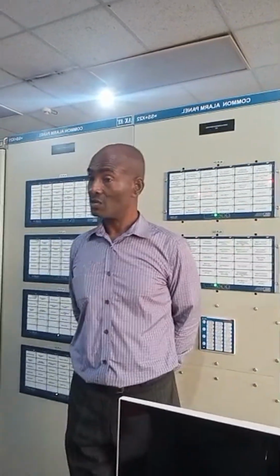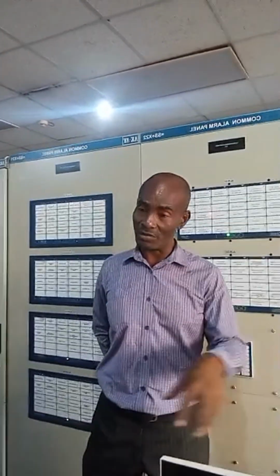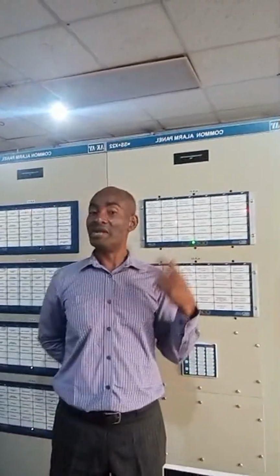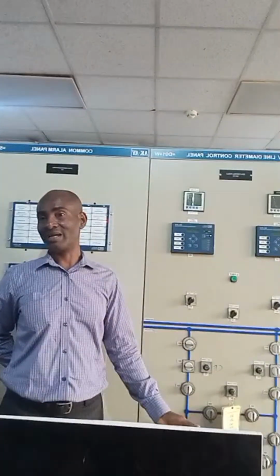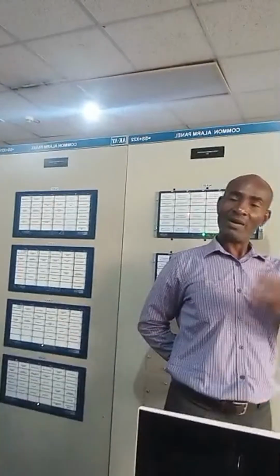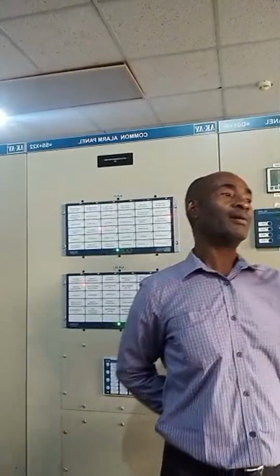Is that okay? You get the gist? If there is no quenching medium, for those highly rated breakers, that's why we have oil circuit breakers, OCB. Inside the OCB you have minimum oil and bulk oil. Oil circuit breaker is a type of circuit breaker used in power systems. Inside the oil circuit breaker, it's divided into two: minimum oil circuit breaker, MOCB, and bulk oil circuit breaker, BOCB.